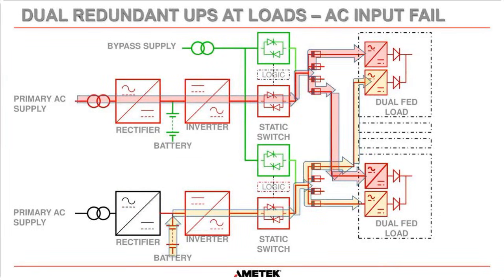And the power flow for this is, once again, if we have a primary AC failure on UPS-B, we just go to battery. Remember, there's no switching. The inverter doesn't care. It's still getting its DC, and it will feed power into the power supplies related to that system. So it's as if nothing happened. You'll get an alarm on UPS-B, but the load circuits will see it as if nothing happened.